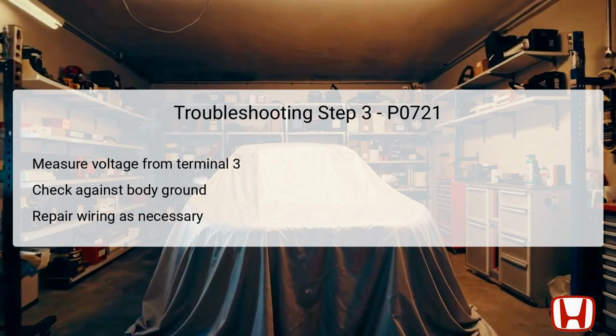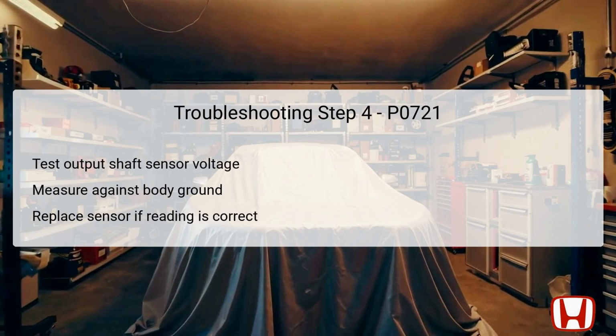Conversely, if the voltage is not as expected, it indicates an issue with the VCC1 wire itself. In this scenario, you should work on identifying and repairing any open circuits in the VCC1 wire for effective troubleshooting. In step 4, you will determine if the problem lies with the output shaft speed sensor itself. Begin by making measurements similar to the previous steps.